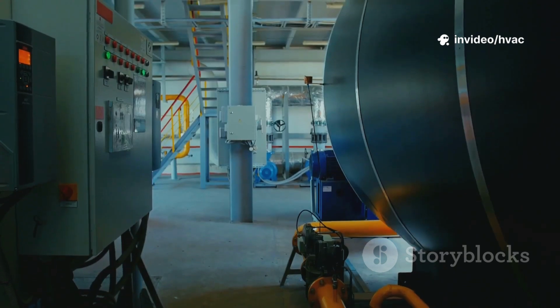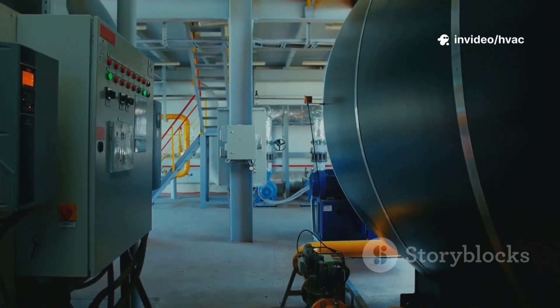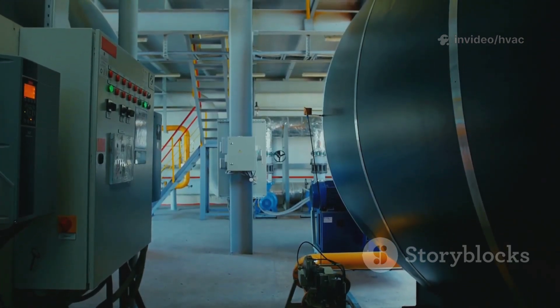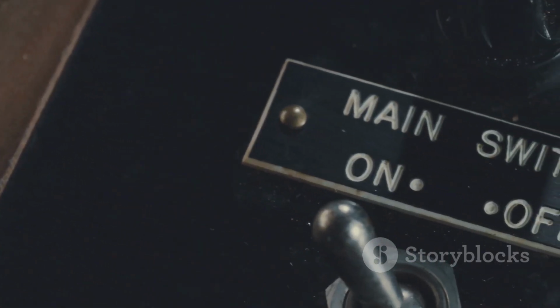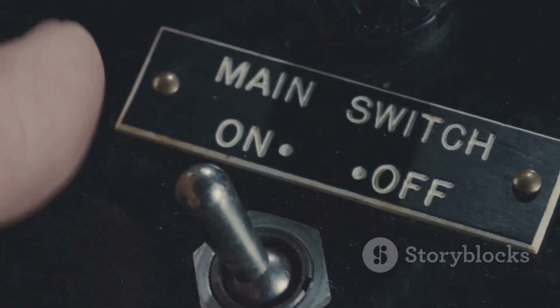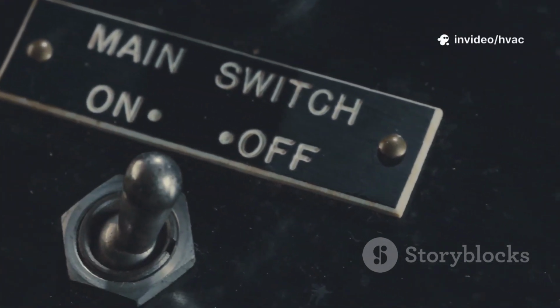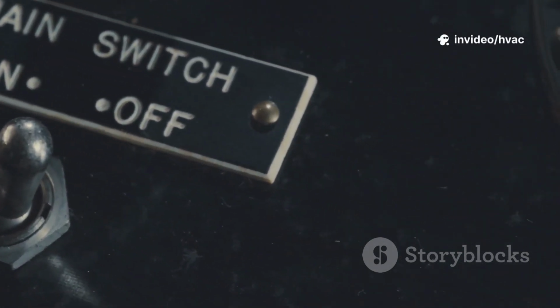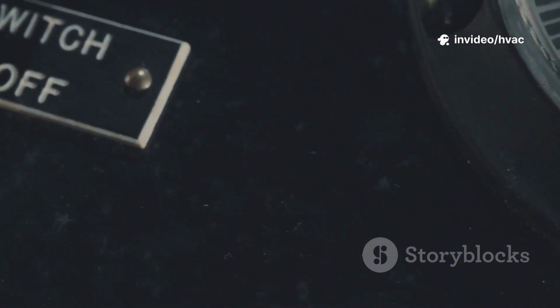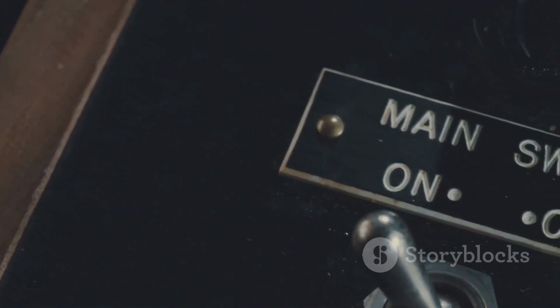But sometimes you want the system to fail safe. That's where NC contacts come in. For example, a boiler's airflow switch might use an NC contact. If the fan fails or a wire breaks, the NC contact opens, breaking the circuit and preventing the boiler from firing. This way, any failure, power loss, broken wire, or device fault results in a safe shutdown.